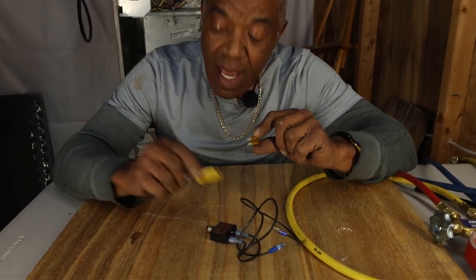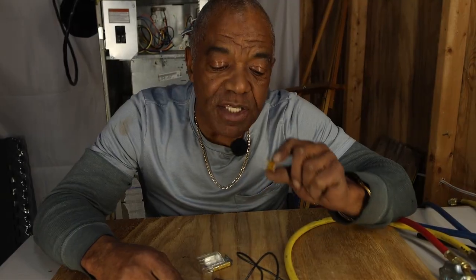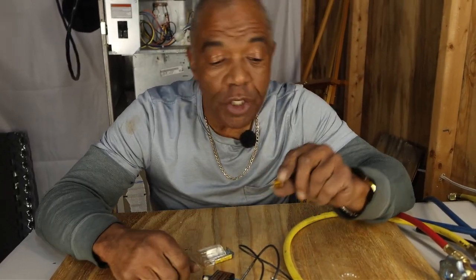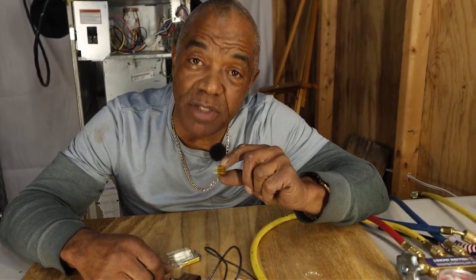These fuses, I get a box of 6 for about $2. So I sell them $6 each. But sometimes they fail not because they're old. They fail because something has shorted out in the system. And every time you turn the system on, the fuse blows. So while you're trying to diagnose and trace that short, you keep putting fuses in. You done used 12 fuses and you still ain't figured the problem out yet.